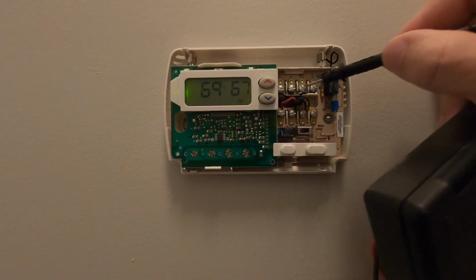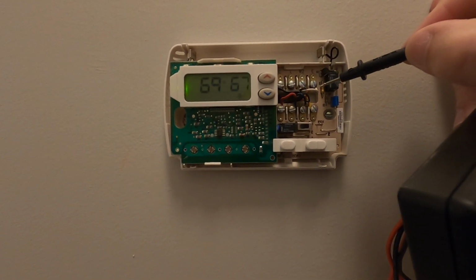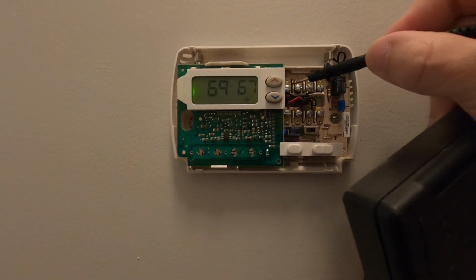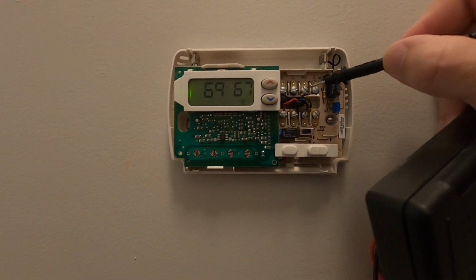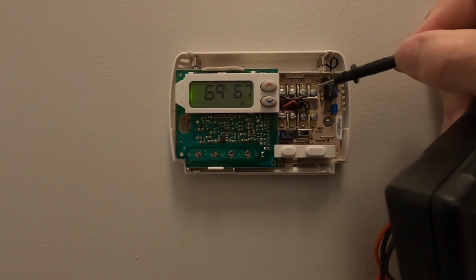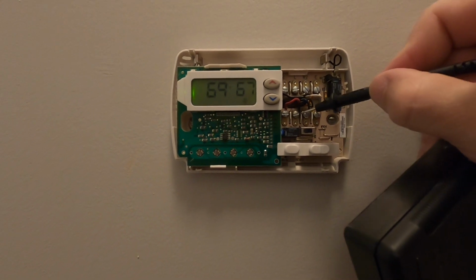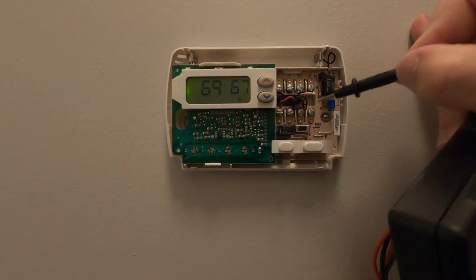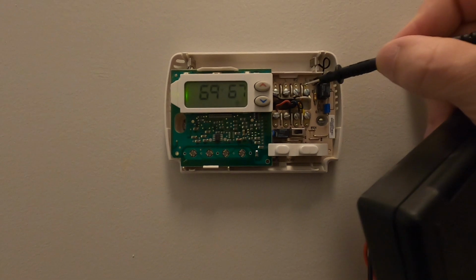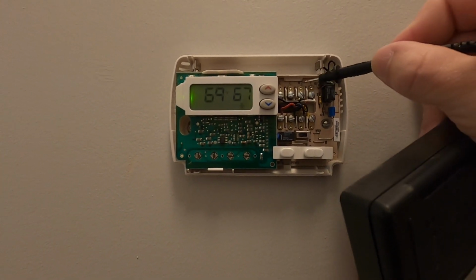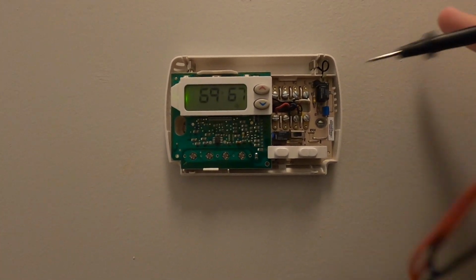So we're going to jump these terminals and check for voltage here, because if we have voltage here, we know something is calling for the emergency heat to come on. The yellow should be on, the green should be on, but mainly we're looking at this white W2 and E terminal here to see what's going on.